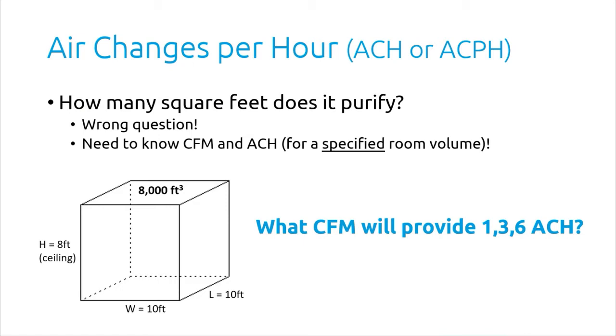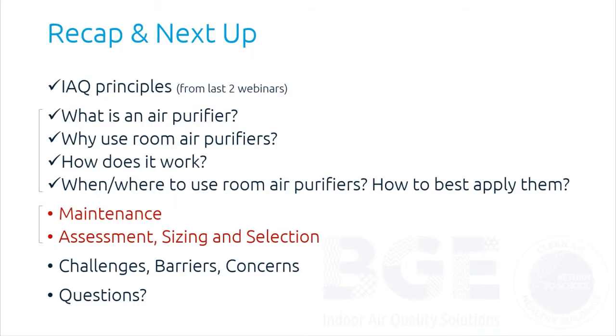Well, how many square feet does it purify? That's the wrong question, because when you look at square feet of a space, that means nothing. How many air changes do I need in that space? If I have 10-foot ceilings versus 8-foot ceilings, it's a different volume of air. So 1,000 square feet is a meaningless spec unless it also tells you it's based on this ceiling height and this many air changes per hour. Does that make sense? I hope it does. And that pretty much wraps up my portion of the walk through this forest of information, and I'll turn it over to Randy.